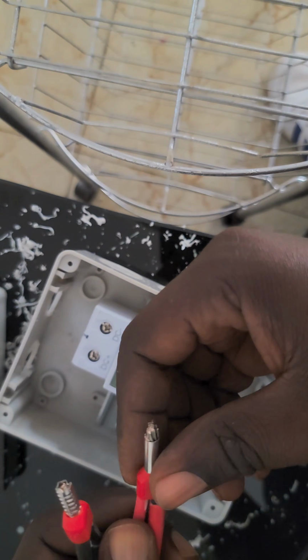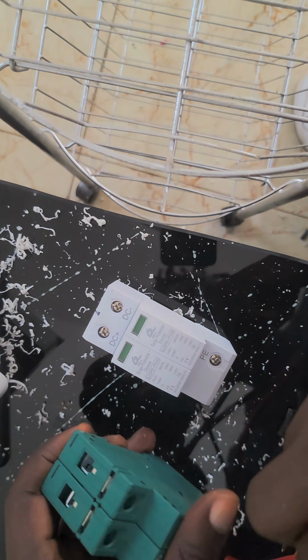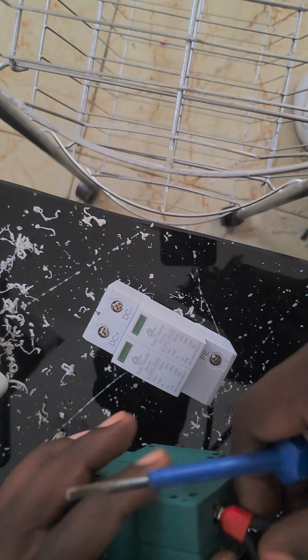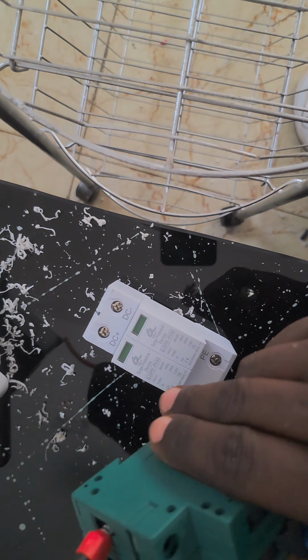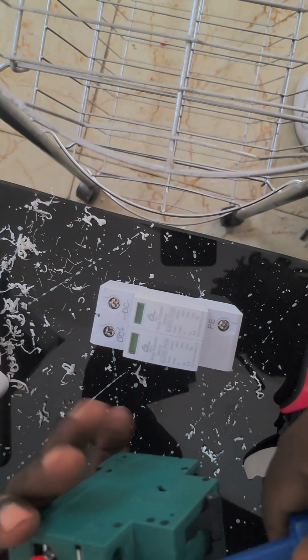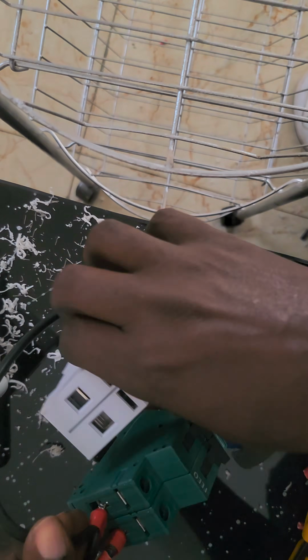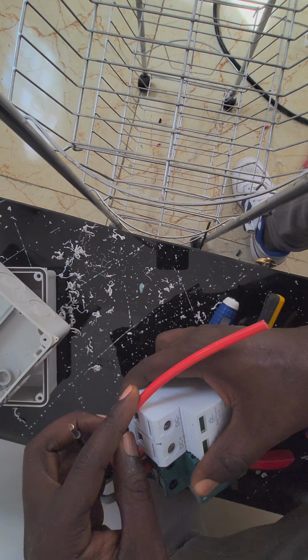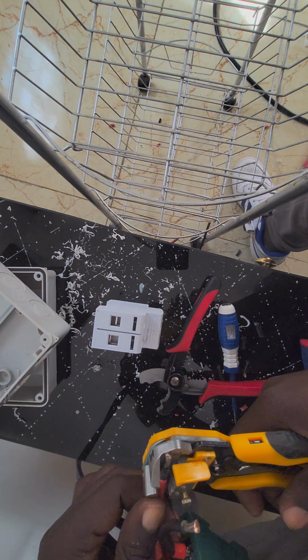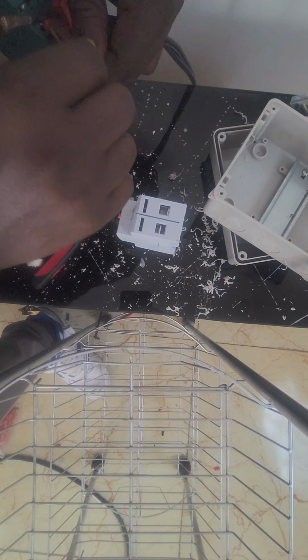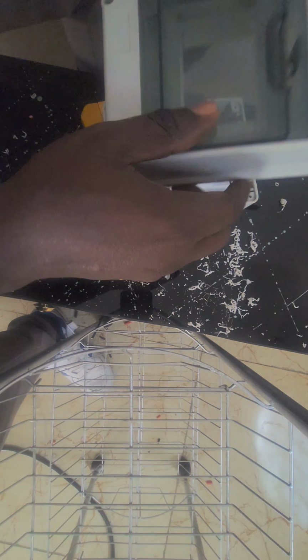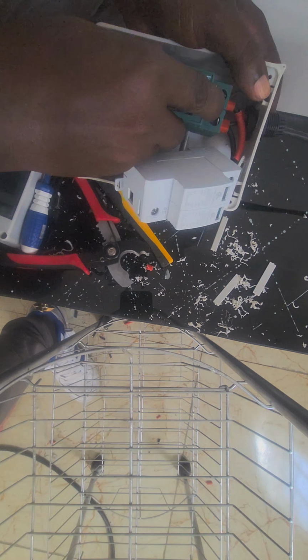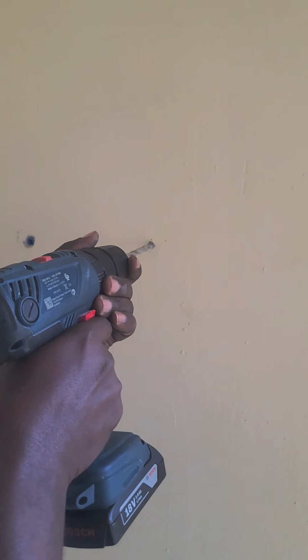The DC breaker's job is to protect from overcurrent, that's if there's overcurrent coming from the solar panel. It isolates the inverter from that current. And the surge protection also protects from things like lightning surges and all of that. So you need to pair them together. They work hand in hand. I have a video where I also set up a combiner box, so you can watch that. I think that's a bit more detailed. So I'm putting them together in this breaker box and connecting the cable that will go to the inverter.